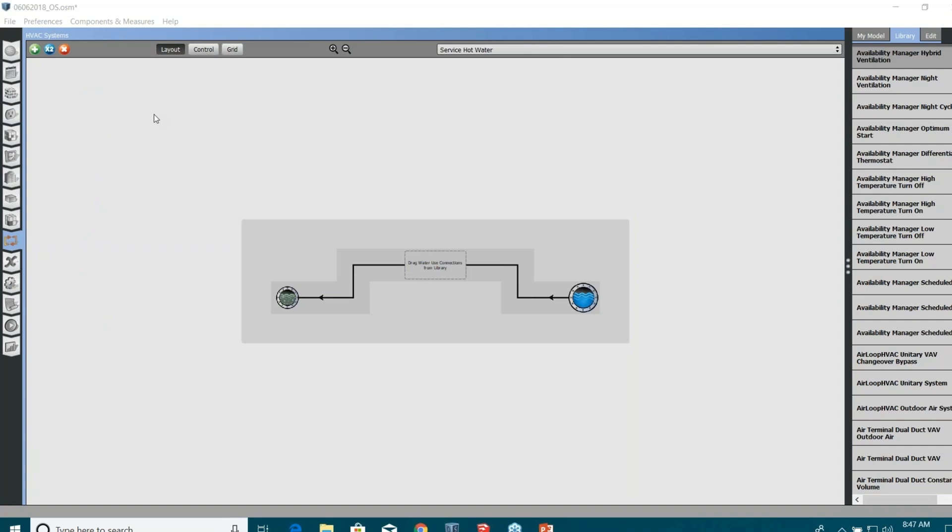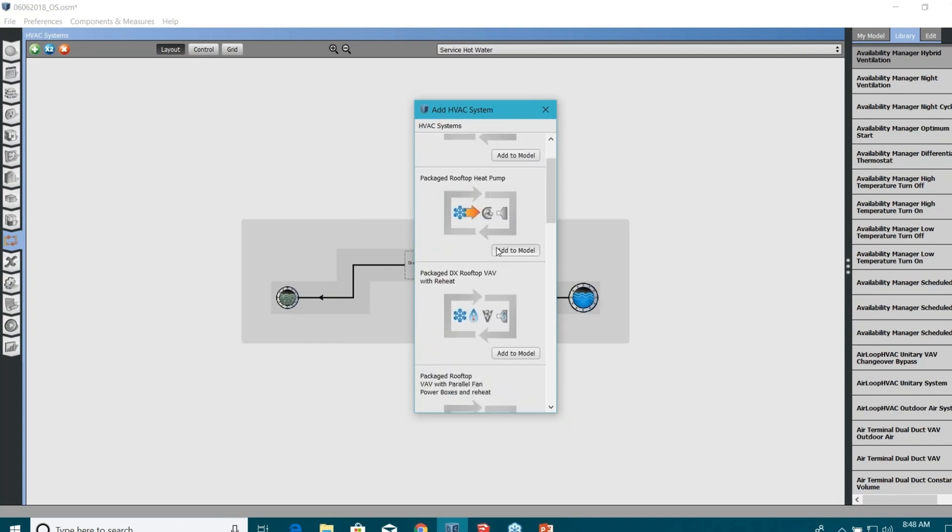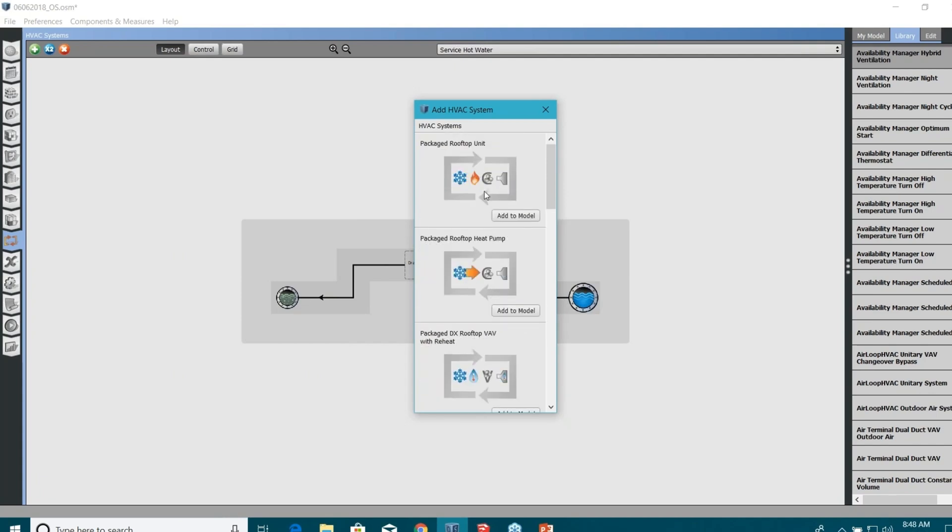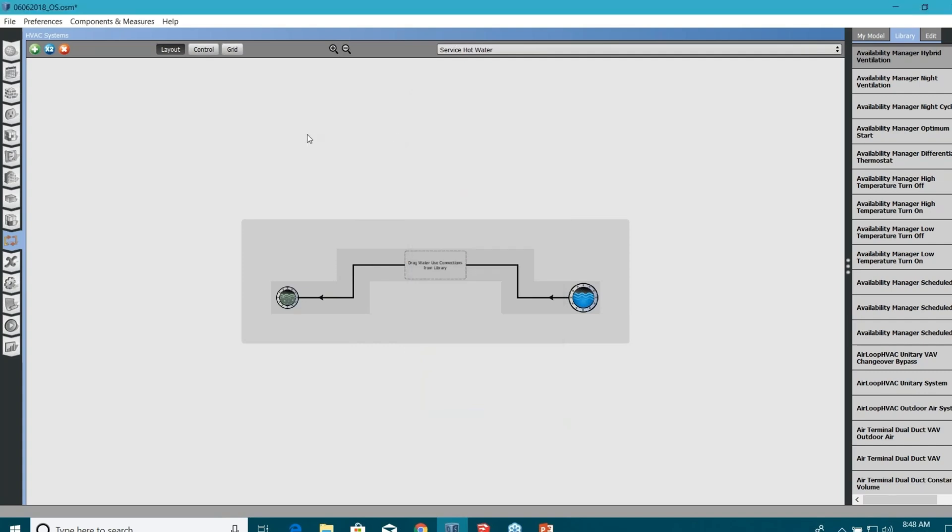There are a couple of ways to create the HVAC systems. Either you can create these templates based on ASHRAE 90.1 Appendix G, all those options, something like packaged rooftop unit, packaged rooftop heat pump or VAV. When you click on these, it brings all the associated properties for you based on Appendix G. Or you can actually use another very important feature here, which is using the OpenStudio measures.